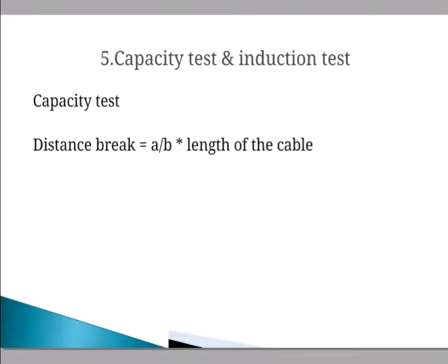This particular method is suitable for locating faults in non-sheathed cables. Because of the armoring and the cable shield, the magnetic field is blocked, no current will be induced in the search coil and no audible sound will be heard. Therefore, this test is unsuitable for locating the fault spot in the core of armored and PILC cables.